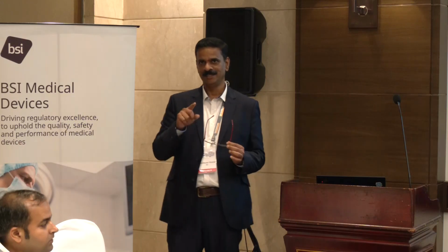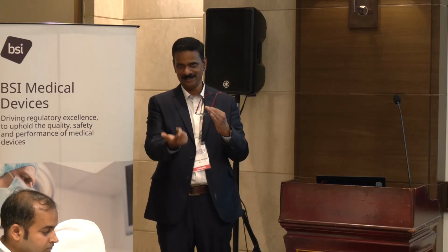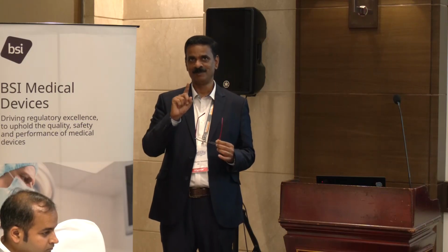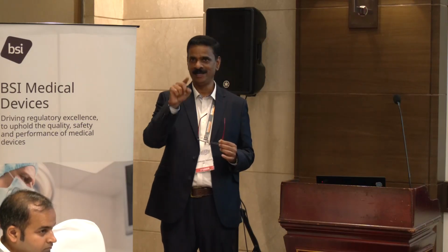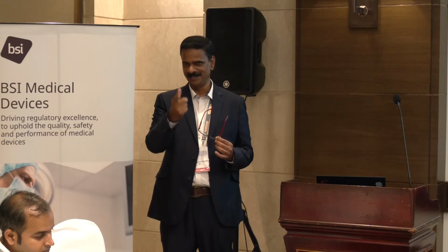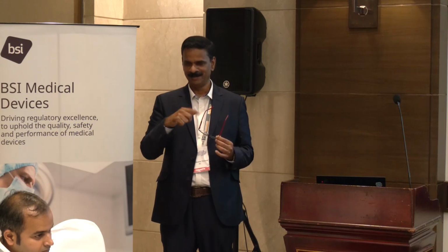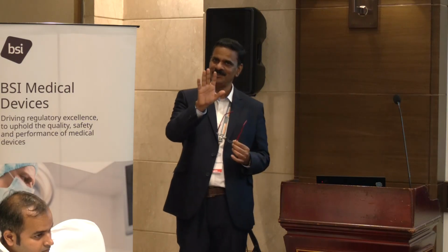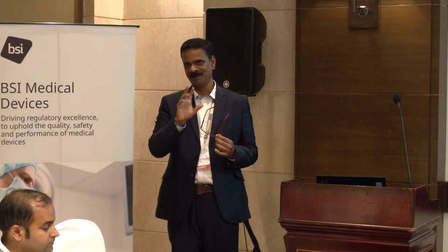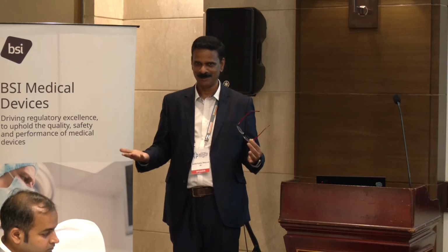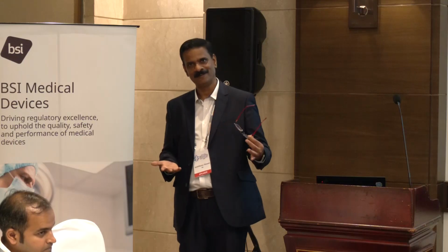Okay. Then you are going from mechanical to electrical. Software also we are updating. So this might be raised by your reviewer because it is a design change itself. I don't know how much risk factor will come in. I don't go into the details, but you need to consider that. So the reviewer may ask more questions, and it is up to you to demonstrate why you think it is not going to affect safety and performance.